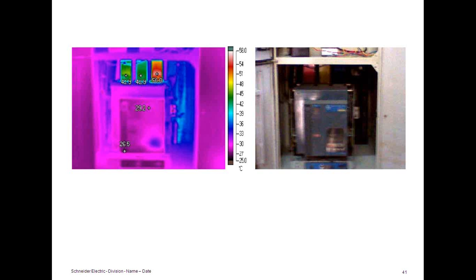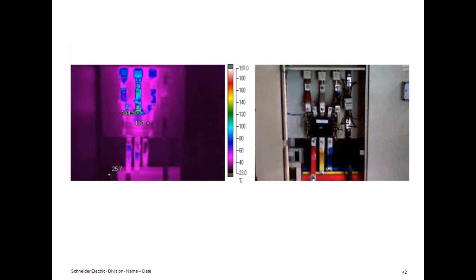These are switchgear feeding the UPS input side. You know, the UPS has a 6-pulse rectifier. I can see that the temperature on the conductor is 194 degrees centigrade. It's almost double the boiling point of water, and it's very dangerous. The insulation is already breaking down and discoloring, and so on and so forth. The loading on this circuit breaker was just 60% of its capacity. Even then, the thermal temperature was significantly on the higher side.